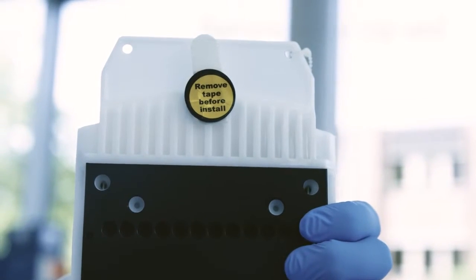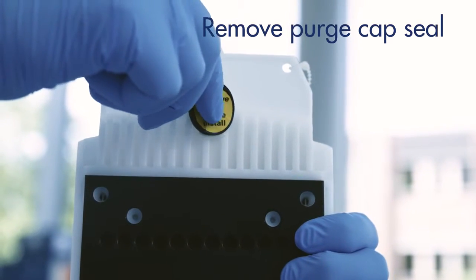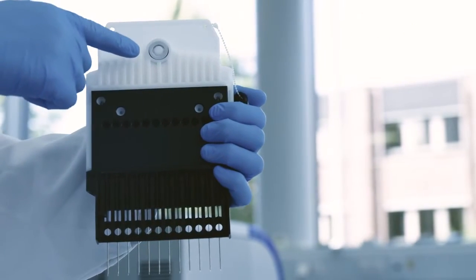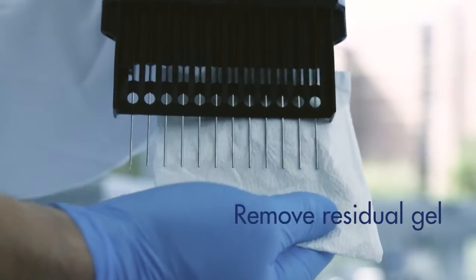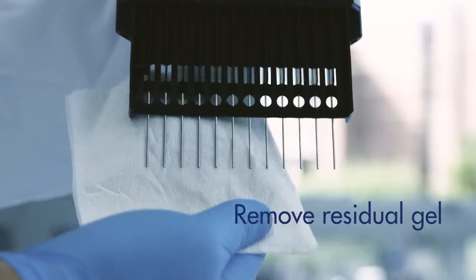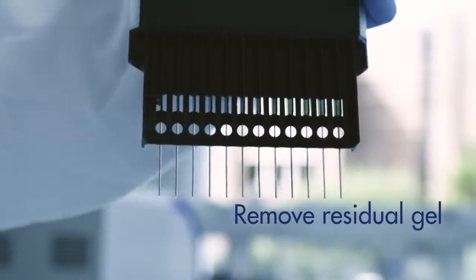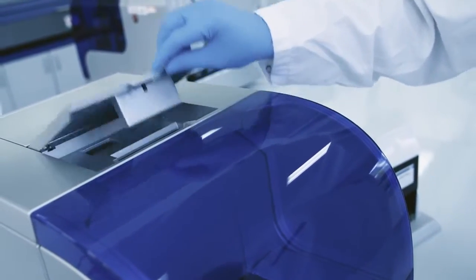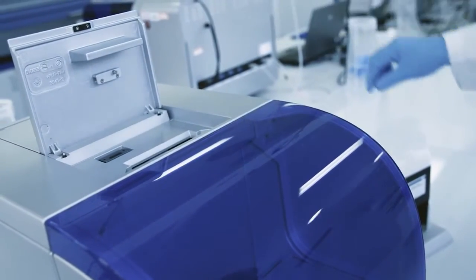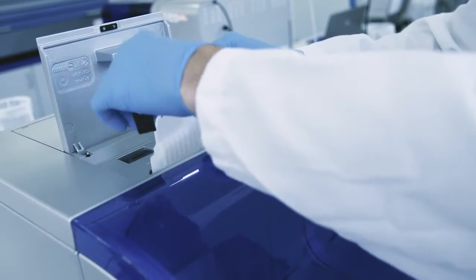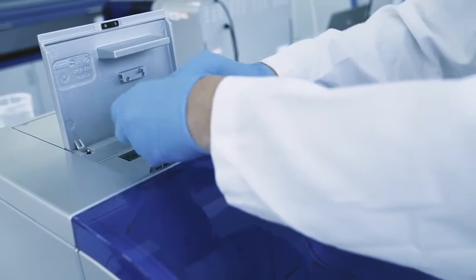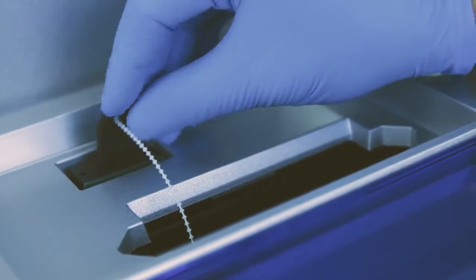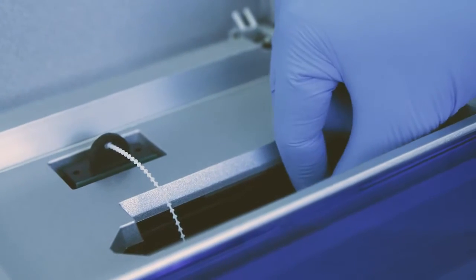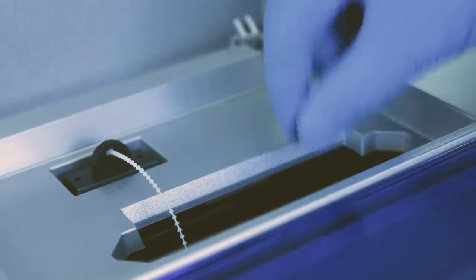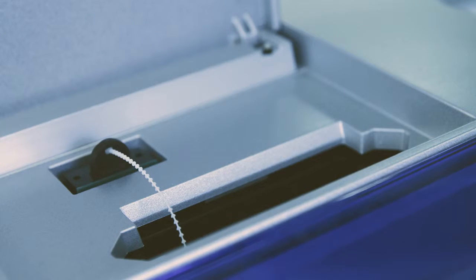Before inserting the cartridge into the QIAxcel Advanced, ensure the purge cap seal is removed. In addition, remove any residual gel or liquids from the capillaries and the purge port. To insert the cartridge, the door needs to be opened. Insert the cartridge with the description label facing toward the front of the QIAxcel Advanced. After that, insert the smart key into the smart key socket in either direction. The system will not recognize the cartridge if the smart key is not inserted.